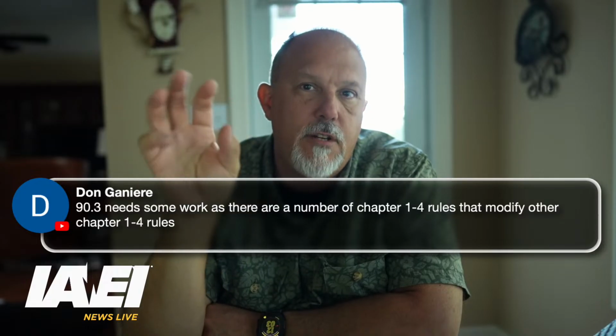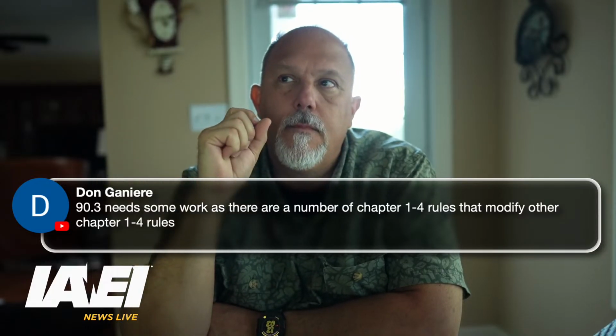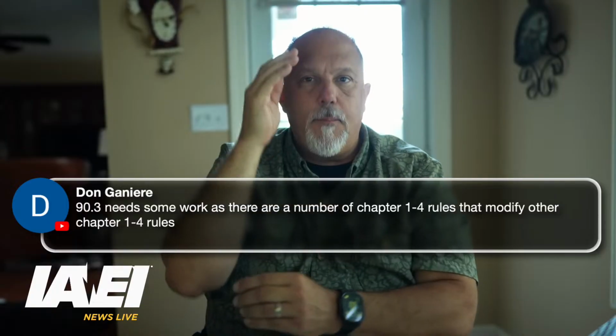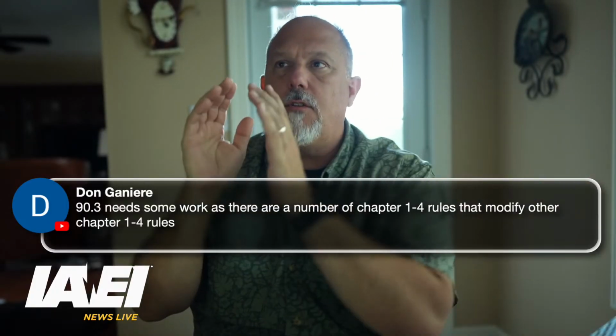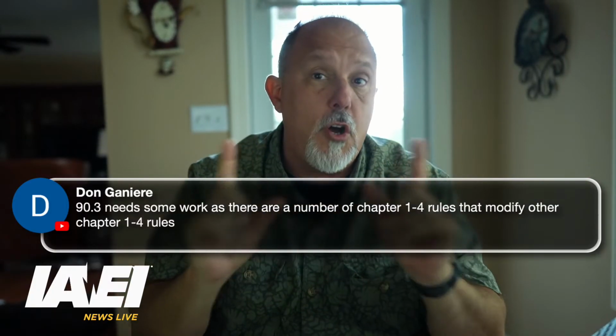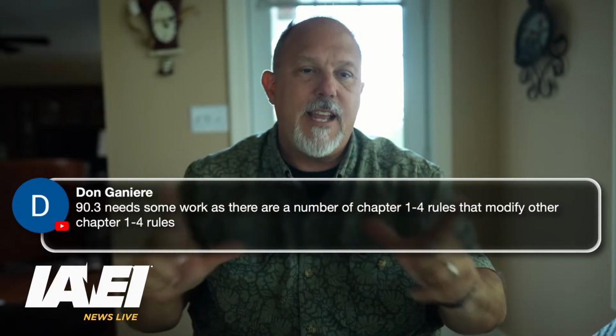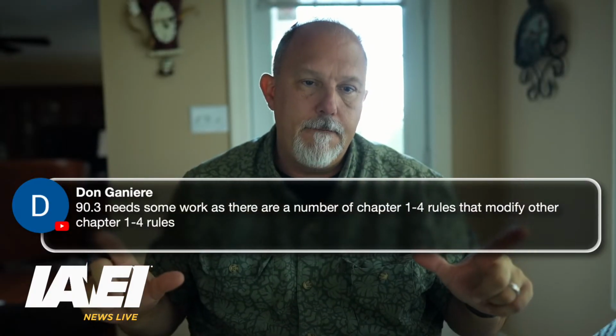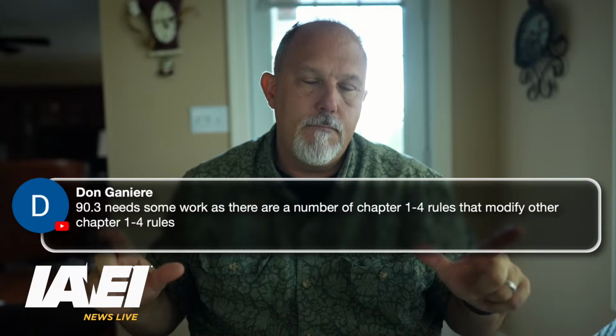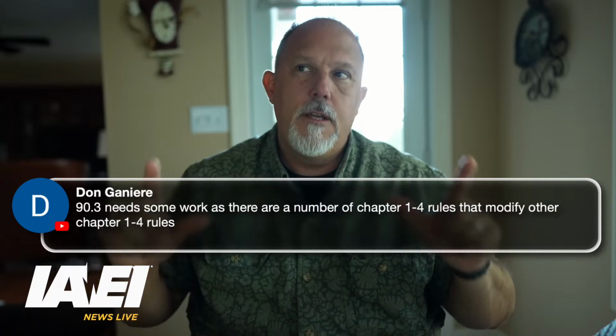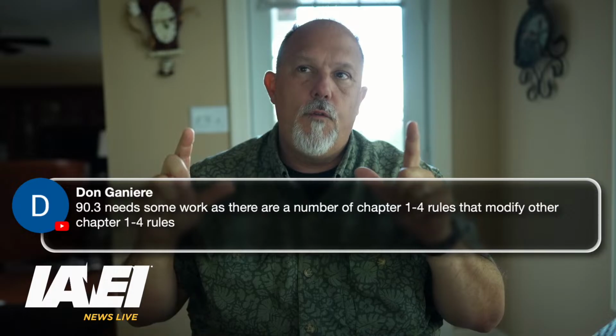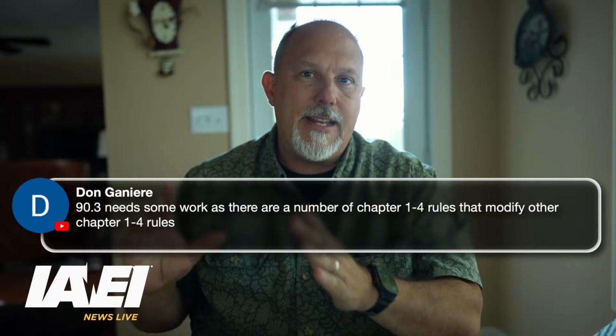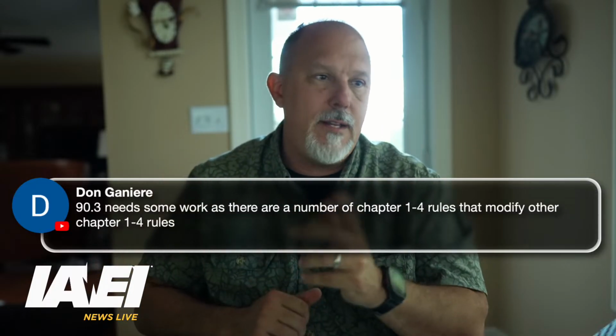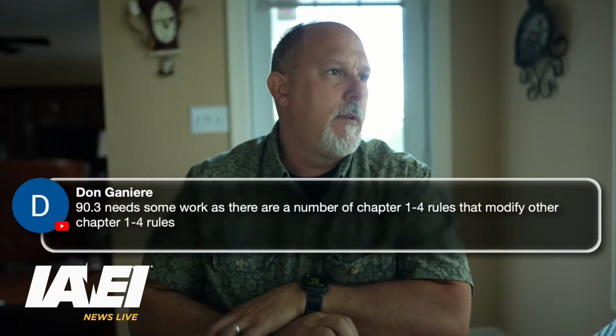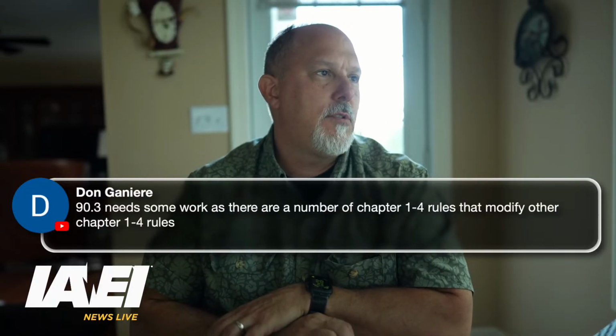But this is a really good example of how, if I have a branch circuit that's feeding a motor, I'm going to go to 430, because it's much more complicated than just saying it's a continuous load. 430 has some intricacies, and honestly, that's equipment for general use.